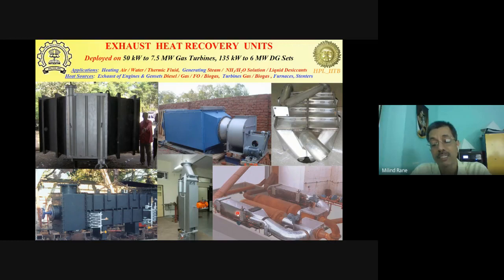The best part was that the pressure drop across this heat exchanger was less than the pressure drop in the muffler. So there was no additional back pressure on the engine because of the unique design. And these heat exchangers were very easy to clean because the gases passed through straight tubes. The heat exchangers had the advantage of combining the benefits of a gas tube boiler and a water tube boiler. The inventory of 1000 kVA genset exhaust heat recovery, on the water side, was less than 18 liters. And in those days, almost 20 years ago, these units would qualify as a non-IBR unit, even for a 1000 kVA genset.